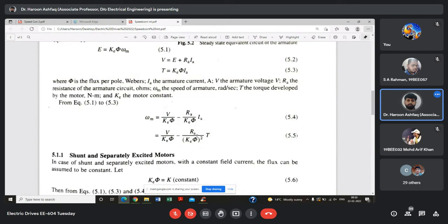इफ यू वैरी दिस आर ए, हाउ दिस कैन बी वैरीड मैथमेटिकली, तो आप इसे कम ज़्यादा कुछ भी करते रहिए, बट RA can never be decreased, because once a machine is manufactured or fabricated, in that case whatever resistance of armature is there inside the winding, that cannot be cut out anyway. वो winding रहने वाली है और उसमें उतना ही resistance रहेगा. So you can always increase the resistance by putting an extra resistance in series with this armature circuit. So the net resistance will come out to be RA plus R external से. ये जो आपके पास RA है, ये net effect इसका RA plus R external हो जाएगा.